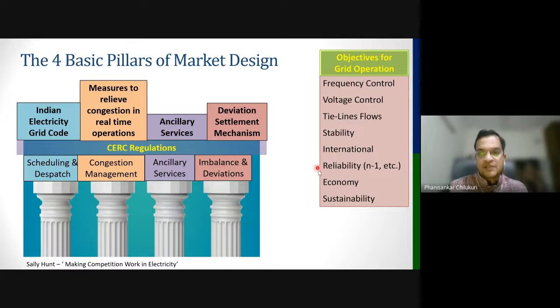We also look at international flows and reliability, particularly n-1, and sometimes n-2 for special cases. When I say n-1, when one element is out, the system should still survive without the need for large scale changes in the plan. There should not be any oscillations or violations in the grid. That is called n-1, and we always ensure that the system is n-1 compliant.